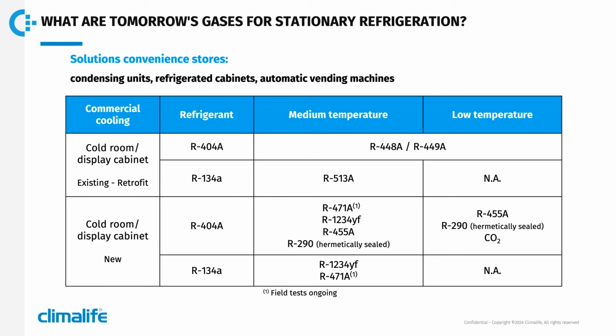For convenience stores, next slide please. We find the same solutions as in supermarkets, with in medium temperature the HFO 1234YF for hermetic compressor. So you can see that we have 5 refrigerants with GWP of less than 150 to meet all your needs. The choice will depend on safety criteria, flammable or non-flammable, and the cost of the installation. It depends on whether we are using a refrigerant suitable for traditional installation with no new technologies, or for super optimized installation but with a higher cost and a lack of technicians who know how to operate them.